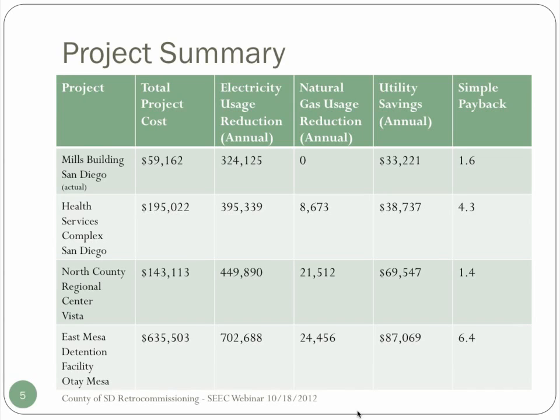What we were able to do with the measures in a little more detail was the chillers, two screw chillers, they were manually operated. We were able to put in place automatic sequencing that was actually part of the controls but disabled. We were able to do a chilled water reset, another feature of the control system that was in place but not enabled. Condenser water reset, the condenser water was pretty much staying at 80 degrees year-round, plus or minus 1 degree. Screw chillers like it cooler, can go down to 65 degrees, so we put in a condenser water reset to have savings on that end.